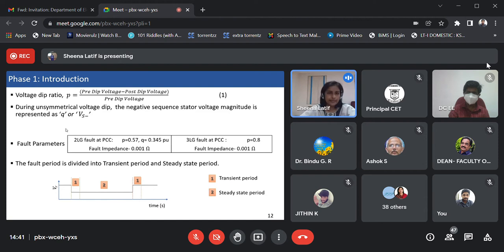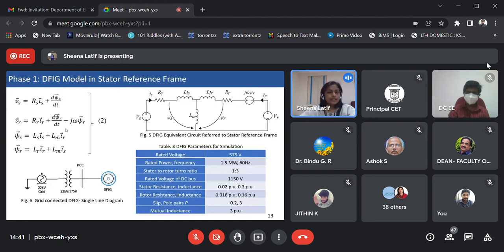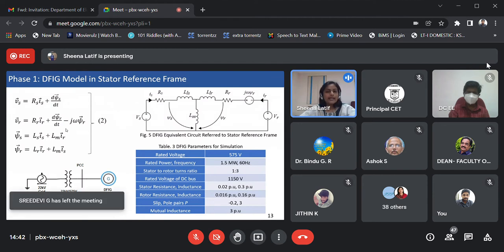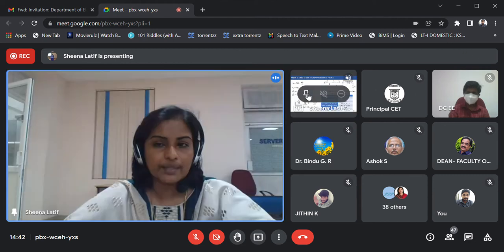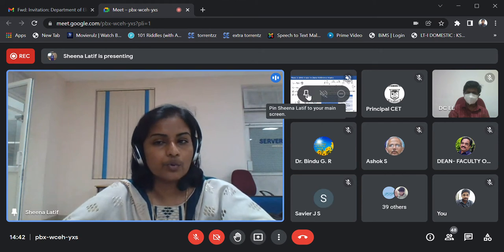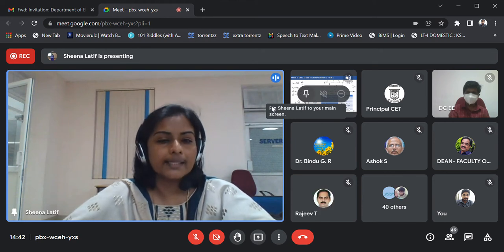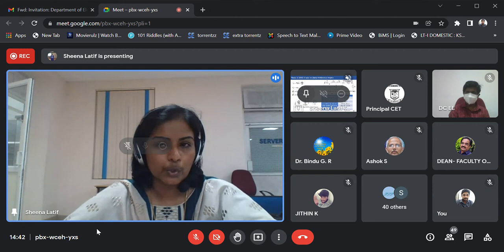and between the two transient periods is the steady state period. The DFIG for analysis is modeled in the stator reference frame based upon the fundamental equations of stator voltage, rotor voltage, and stator and rotor flux, and the equivalent circuit of the DFIG obtained is shown. The single line diagram of the DFIG considered for simulation and analysis, a 575 volt 60 hertz DFIG connected to a 22 kV grid, is also shown, and the DFIG parameters for simulation are given in the table.